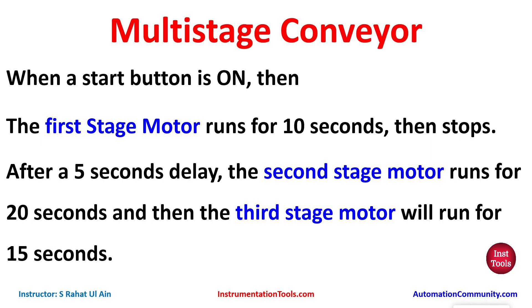Multi-stage conveyor: when a start button is on, the first stage motor runs for 10 seconds then stops. After a 5-second delay, the second stage motor runs for 20 seconds, and then the third stage motor runs for 15 seconds. For motor one we will use a timer TP, then for motor two we will use TON for 15 seconds and then TP for 20 seconds, and for motor three we will use TON for 35 seconds and TP for 15 seconds.